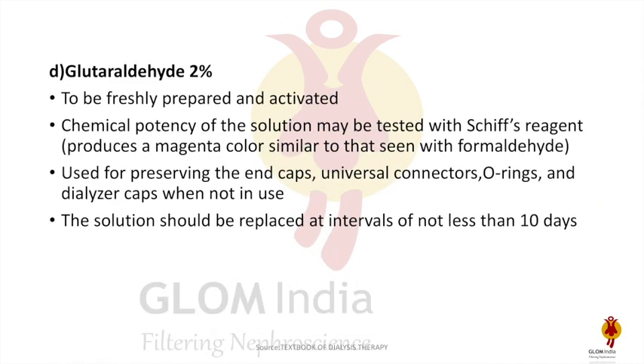Another agent is glutaraldehyde 2% or Cidex. It needs to be prepared freshly and must be in active form. Its potency can be checked by Schiff's reagent, which will produce a magenta color. Similarly, like formaldehyde, it is used to preserve end caps, universal connectors, O-rings, and dialyzer caps when not in use.